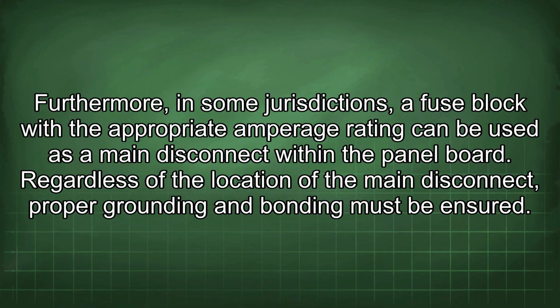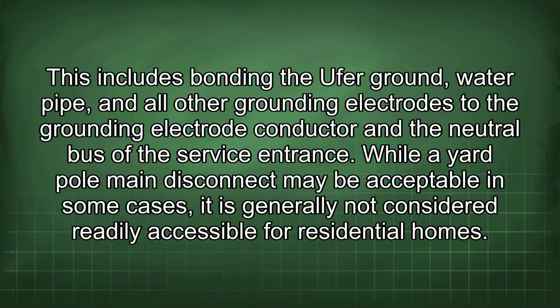Furthermore, in some jurisdictions, a fuse block with the appropriate amperage rating can be used as a main disconnect within the panel board. Regardless of the location of the main disconnect, proper grounding and bonding must be ensured. This includes bonding the UFER ground, water pipe, and all other grounding electrodes to the grounding electrode conductor and the neutral bus of the service entrance.